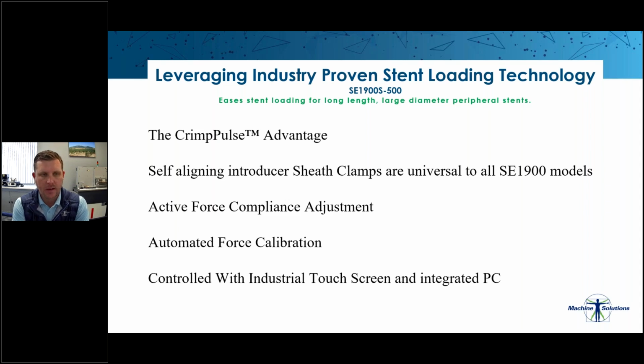During the CAT calibration, the machine builds a CAT table that records the displacement of the encoder for every pound of force exerted against a non-compressible gauge pin. Because the pin does not compress, all variation in the position of the encoder is attributable to the compliance of the system. So this is one of the benefits when you're stent loading nitinol, since it really does want to always try and expand to its original shape.